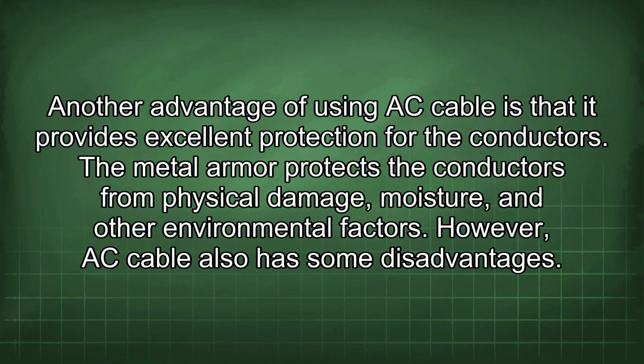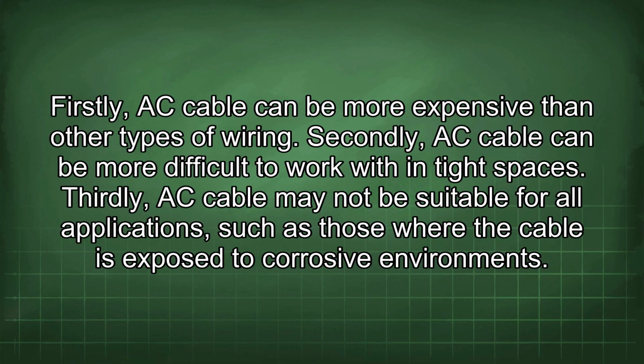Another advantage of using AC cable is that it provides excellent protection for the conductors. The metal armor protects the conductors from physical damage, moisture, and other environmental factors. However, AC cable also has some disadvantages. Firstly, AC cable can be more expensive than other types of wiring. Secondly, AC cable can be more difficult to work with in tight spaces.